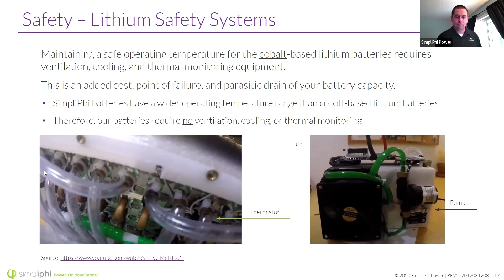So here's that operating range I've been talking about. Operating, let's call that discharging. So we can go as cold as -4 Fahrenheit up to 140 degrees Fahrenheit. You may see other cobalt-based chemistries topping out at maybe 120 degrees Fahrenheit for their operating temperature.